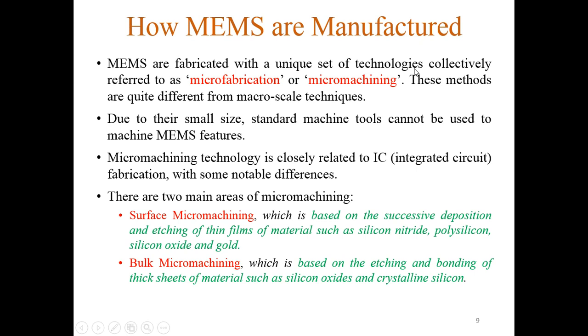MEMS are fabricated using a unique set of technologies collectively referred to as microfabrication and micromachining. Microfabrication comes from the electronics side and micromachining from the mechanical side. These methods differ from macro-scale techniques because standard machine tools cannot be used due to the small feature sizes. There are two main areas of micromachining: surface micromachining, based on successive deposition and etching of thin films such as silicon nitride, polysilicon, silicon oxide, and gold; and bulk micromachining, based on etching and bonding of thick substrates of material such as silicon oxides and crystalline silicon.